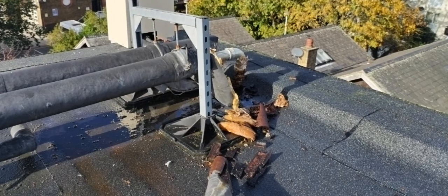So this is a leak on a roof. Hard to find. Sometimes when you see a system constantly filling up and losing pressure, you wonder what's happening, but this was happening because there was a leak on the roof.